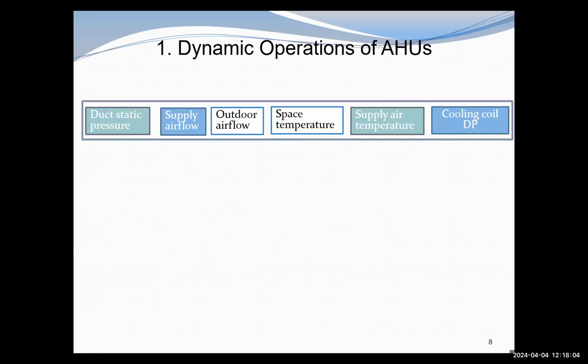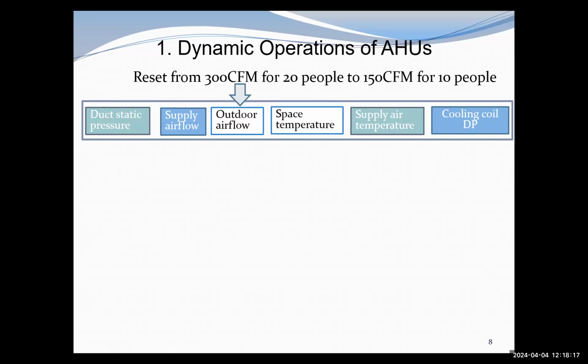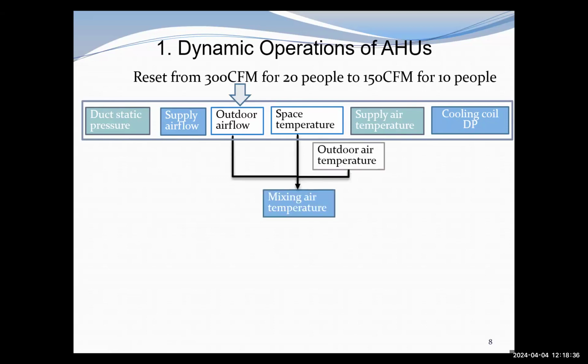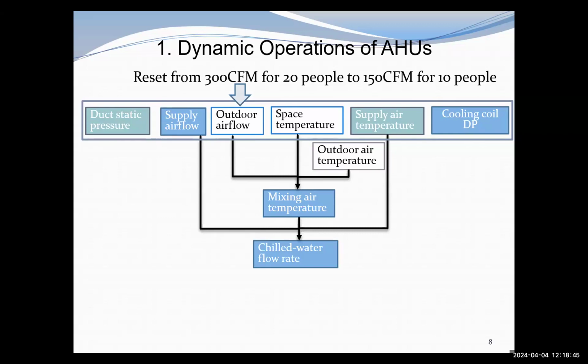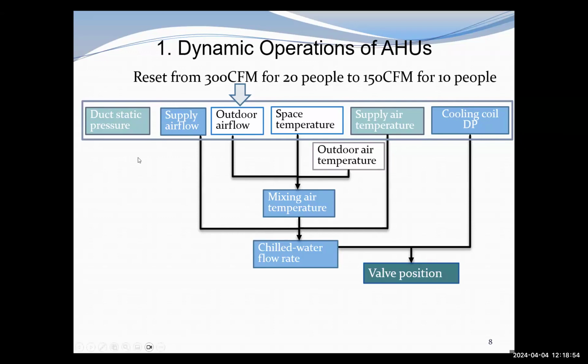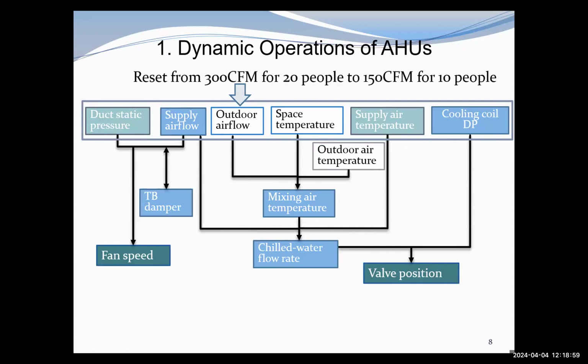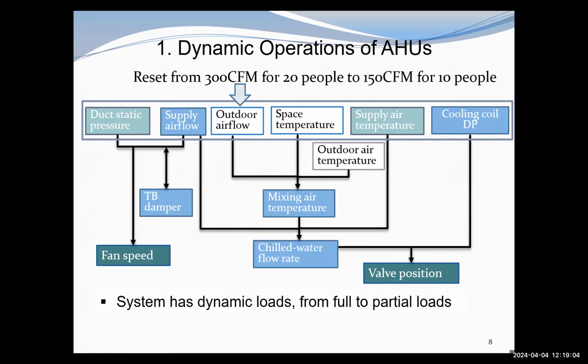Let's see it in detail. These are the six parameters that might be reset in different scenarios. For example, if the number of people in the space is reduced from 20 to 10, then we will dynamically reset the outdoor airflow from 300 CFM to 150 CFM. With this reduced outdoor airflow rate, the mixing air temperature will change. Then with the decreased mixing air temperature, the chilled water flow rate requirement will be reduced, and this will impact the valve position. Similarly, in the fan speed control loop, the damper position will also impact the fan speed control. So we can see that the system is always operated under dynamic loads, from full load to partial load conditions.